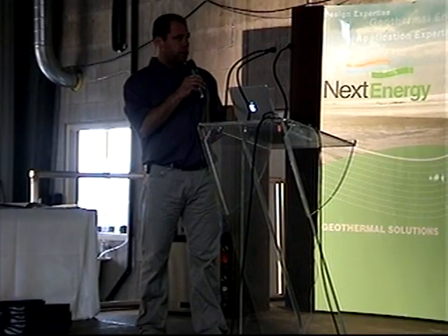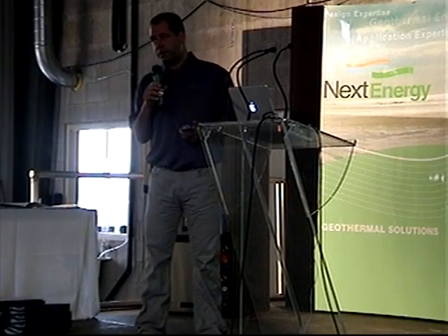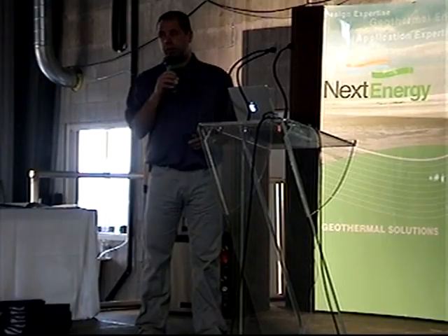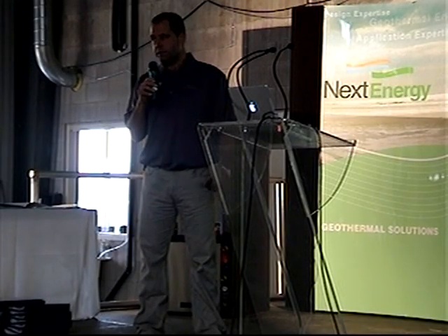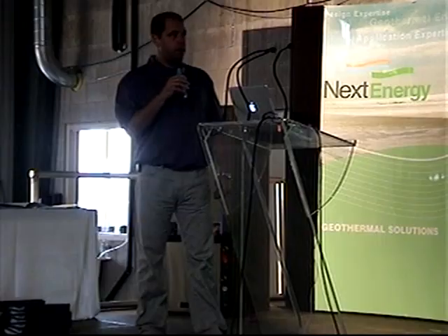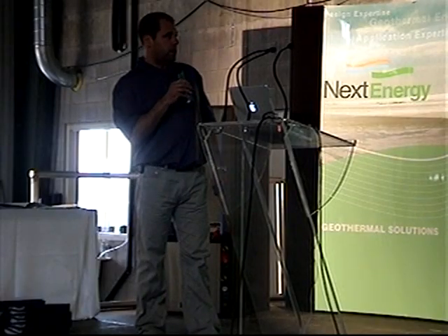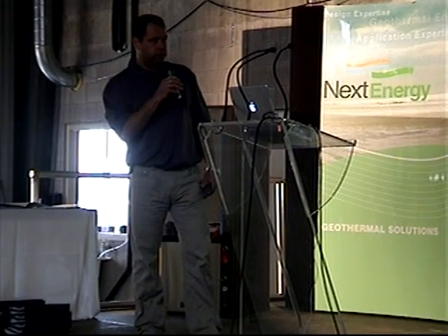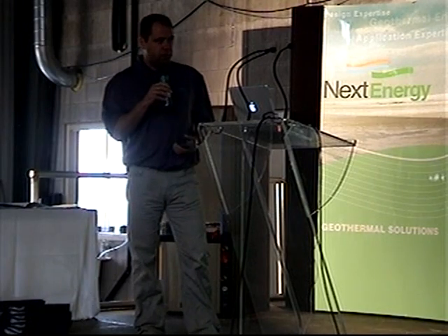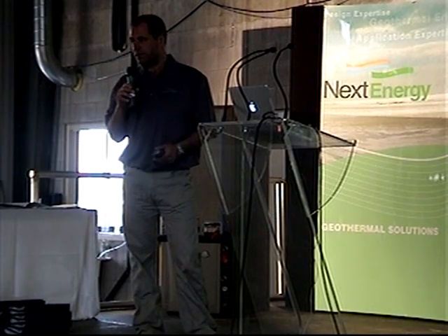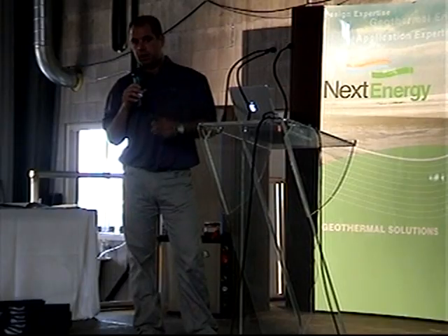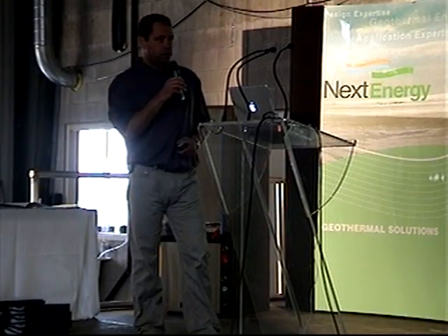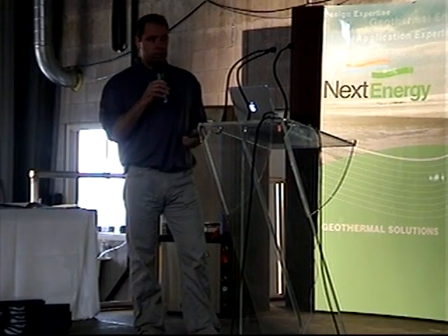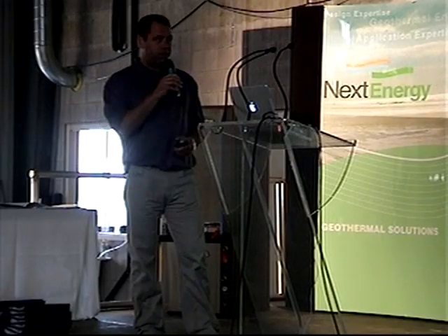Leak detection. Some older leak detectors may not work. They would probably have to be pretty old. Most of the newer leak detectors work with pretty much anything. It requires different lubricants, which you guys probably won't have to worry about unless you're, for some reason, changing the oil, but all heat pumps come with scroll compressors. Obviously, oil comes from the factory. You can't really add oil very easily.